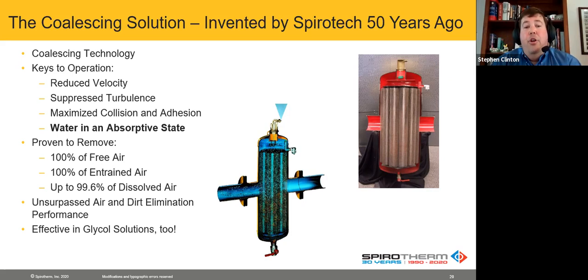Also, in the next slide, I'll show you that the reason why it's called coalescing is the small bubbles like to grab the little edges of the copper fine filaments, and then other bubbles grab others, and as they get more and more, they rise to the top. What happens is, and you can see this when you watch the demo, we can put an air bubble in a free air pocket. The water literally becomes absorptive. It enters the unit with more air than it leaves with when it goes back out into the system. It scavenges all that air to come into the system. All right.